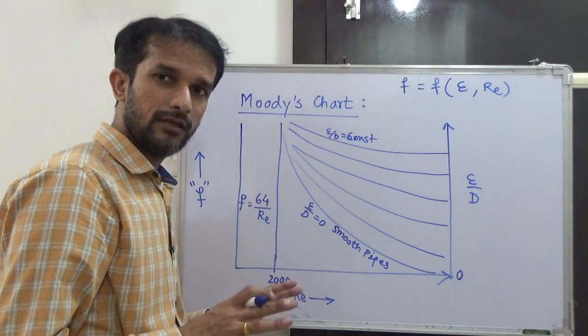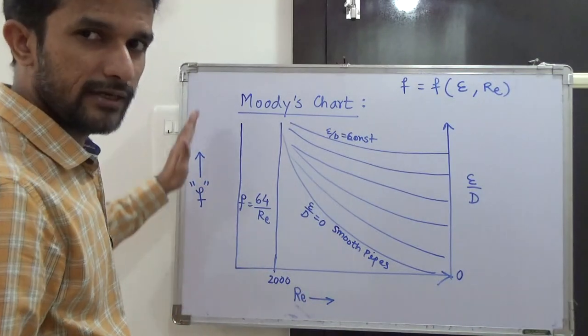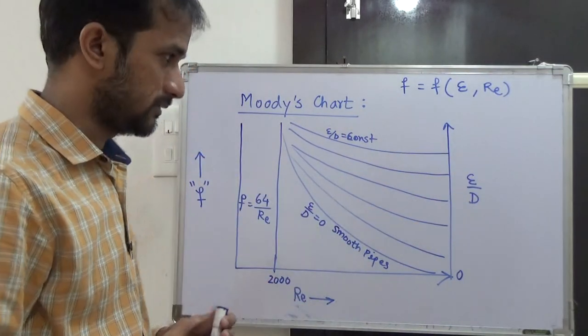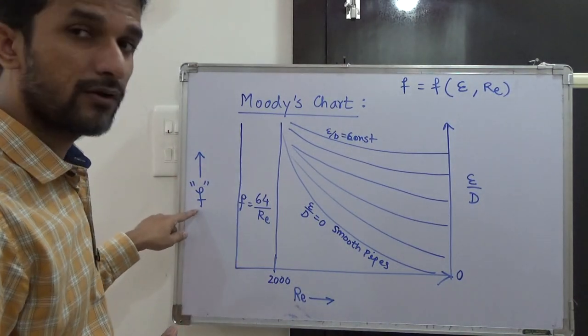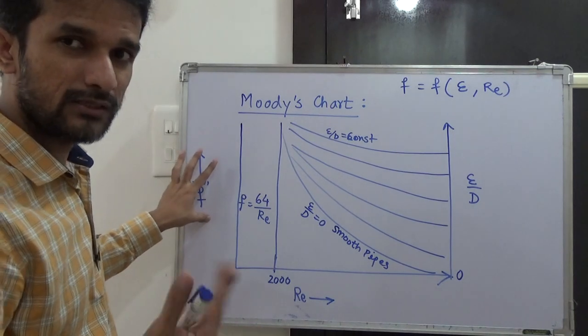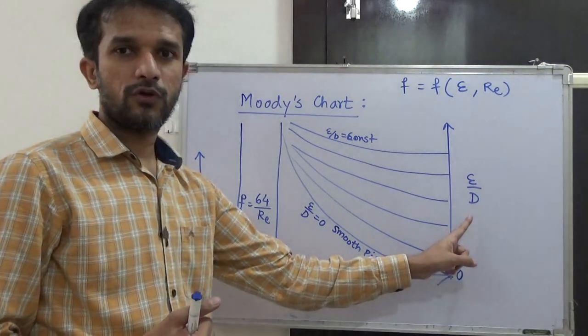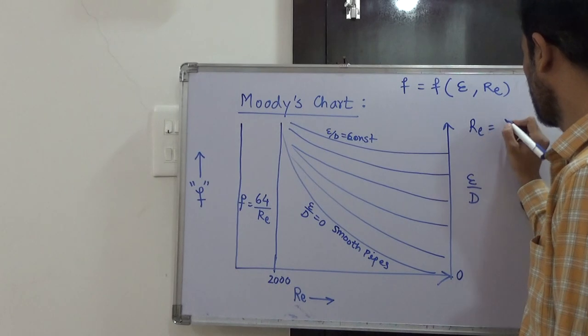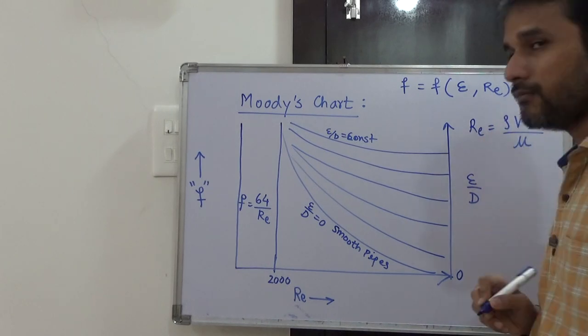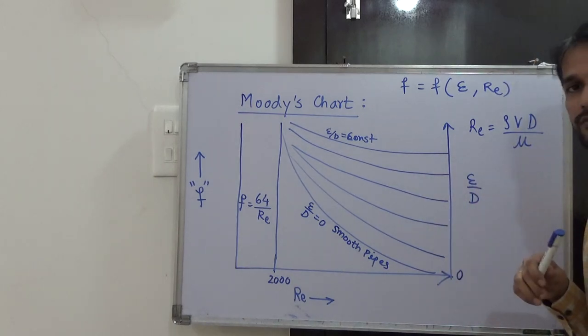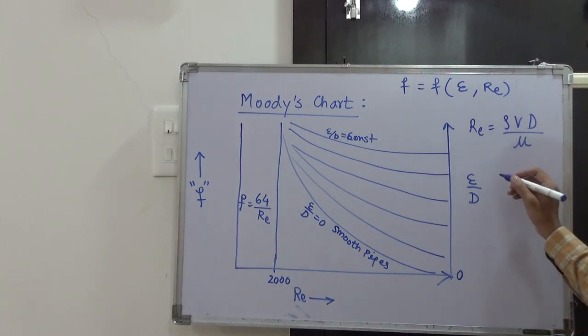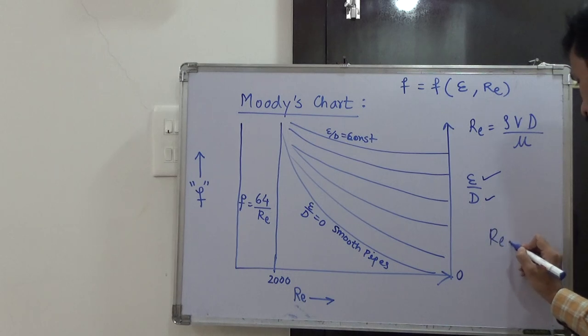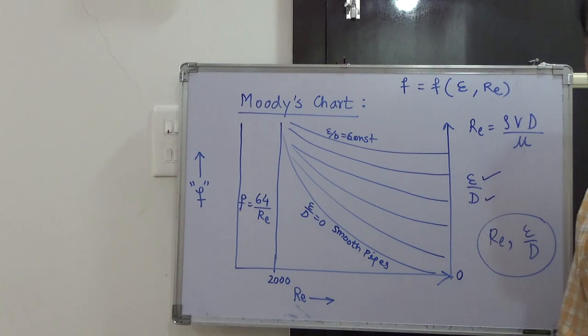To use the Moody chart to find the friction factor, you need two inputs: the Reynolds number and the epsilon/D value. If not directly given, compute Reynolds number using the formula Re = ρVD/μ, where ρ is density, V is velocity, D is diameter, and μ is viscosity. You must also have the epsilon value and the diameter to compute the relative roughness, ensuring both are in the same units.